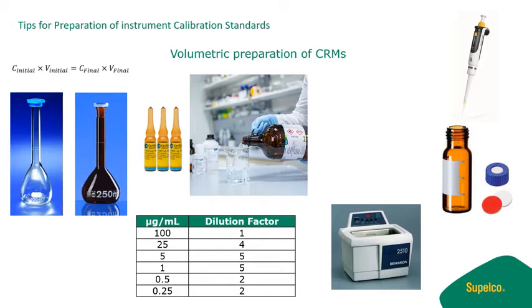It is also important not to introduce additional variables or contaminants into your standards. To minimize this, always use the correct grade solvent for extractions and dilutions. Using an incorrect or lower-grade solvent may yield additional unwanted peaks in your chromatography or provide a high instrument baseline background, which may affect your method's sensitivity. After ensuring you have the required method analytes, solvents, glassware, and sample handling labware, you are on your way to generating calibration standards.